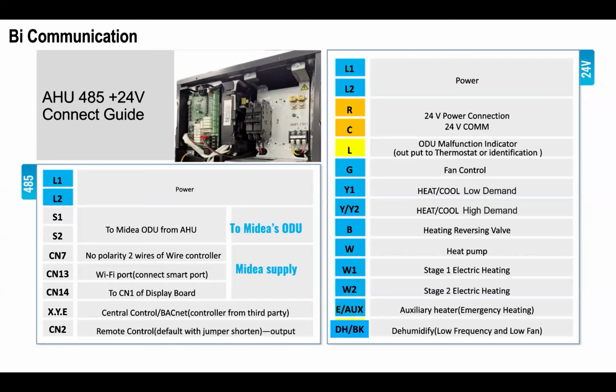G is fan control. Y1 is low demand. Y2 is high demand. B is your reversing valve. We do reversing heating. W is a heat pump heating call, so that is actually an input to the outdoor unit. W1 and W2 are your stages of electric heat. EAUX is your auxiliary heat or emergency heating. And then a DHBK terminal is for dehumidification. Now, the dehumidification terminal is not active for wire control, because we are going to be using the wire control to control humidity.